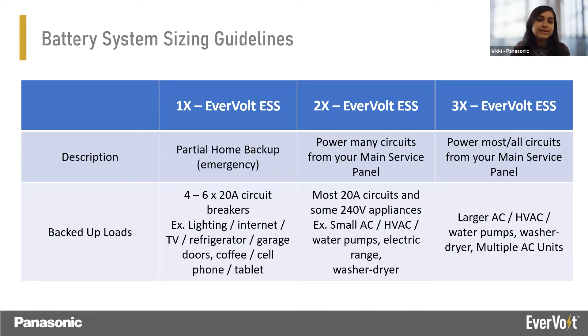These are the numbers based on which we can design the EverVolt loads, or what loads need to be backed up. So this is a conversation that the installer needs to have with the homeowner at the time of planning for the installation to identify how many units they need. So this is the quick math or the quick specs that we need to look into, which is mainly the output power, current, the storage capacity. The storage capacity here determines how long the system can run, but it is also dependent on how many appliances are connected to the system.